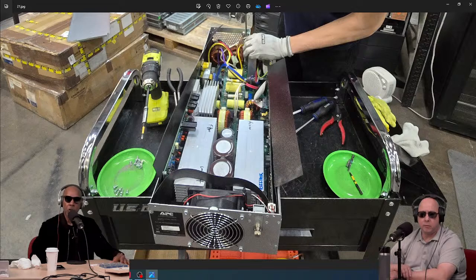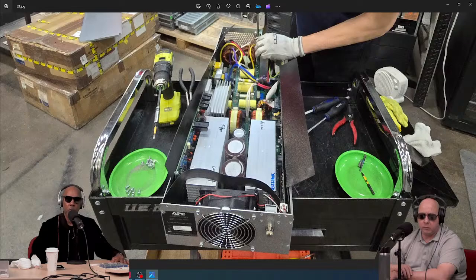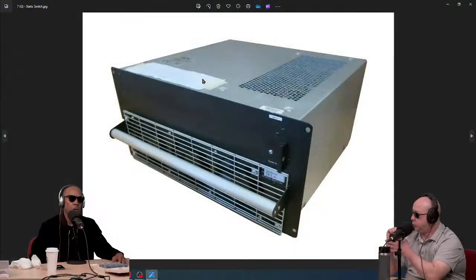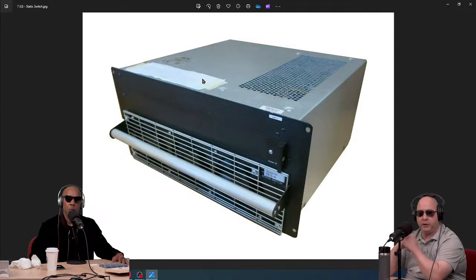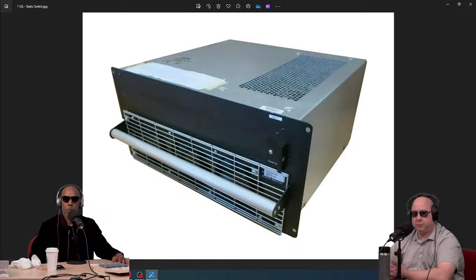All right, let's go to slide G, which is the static switch. What's going on with that static switch? What are you doing in terms of refurbishment? What we do with that is check the configuration card that goes into it, which tells your frame capability. Hold on, what its capacity is, there it is right there. In the top right corner, it's a configuration card that will actually tell the system how it's supposed to be configured. And then the static switch allows us to go in and out of static bypass.